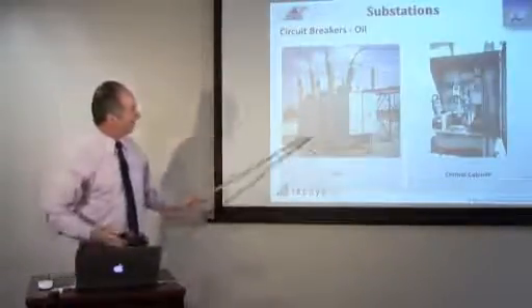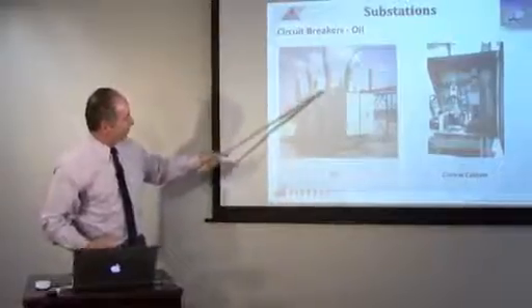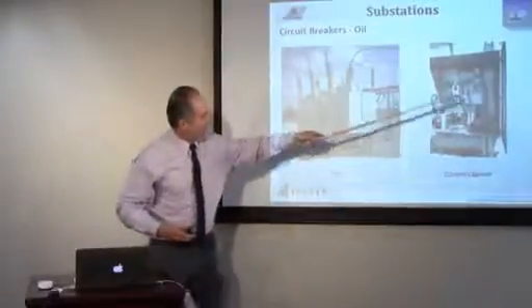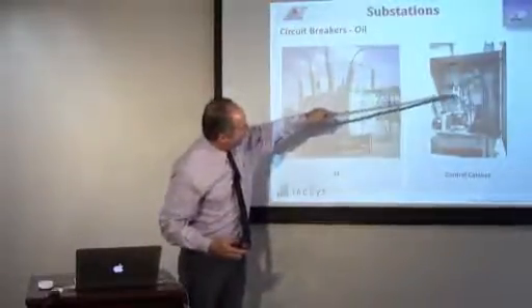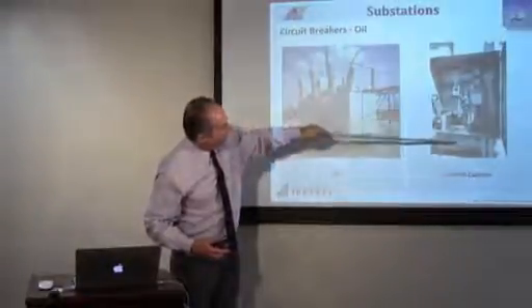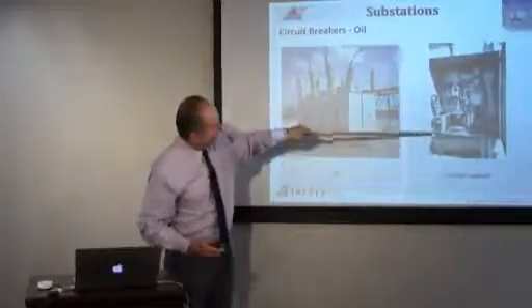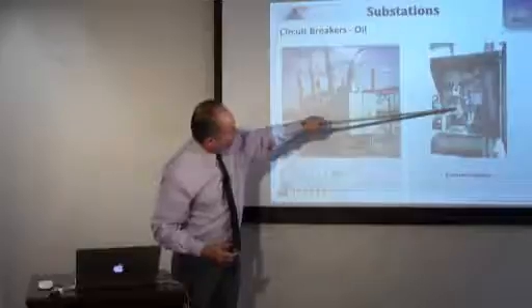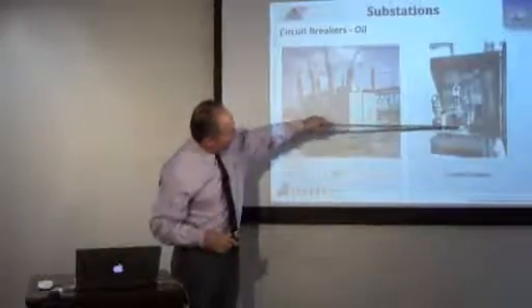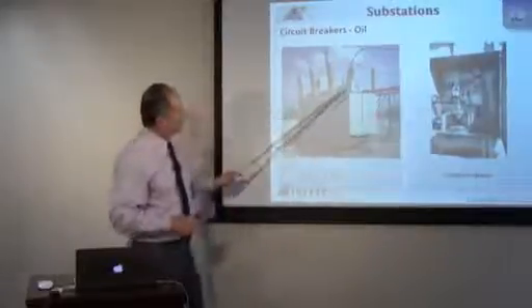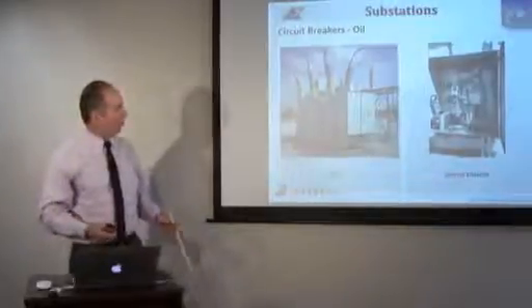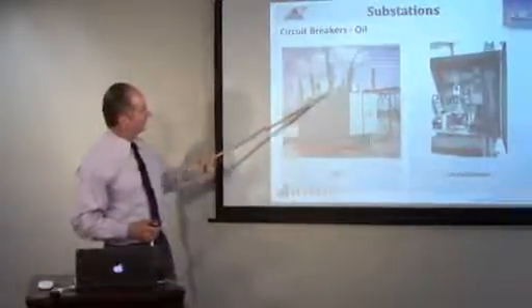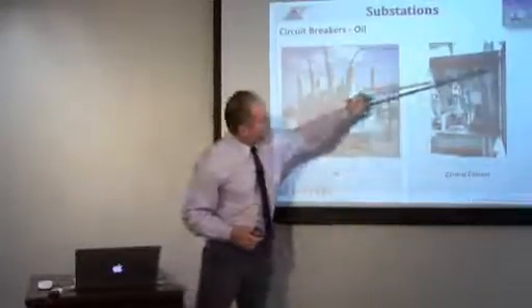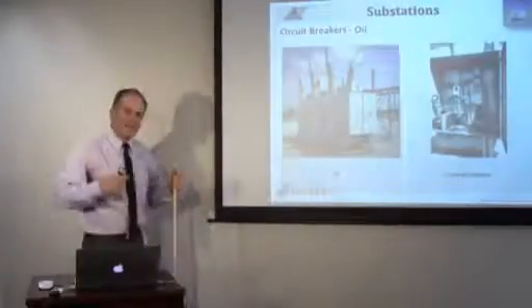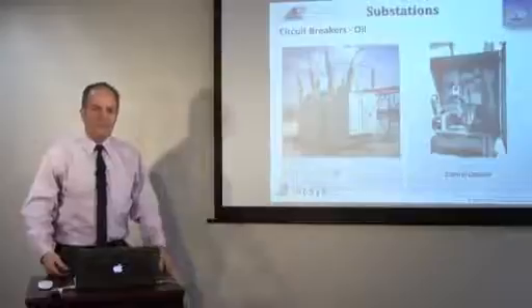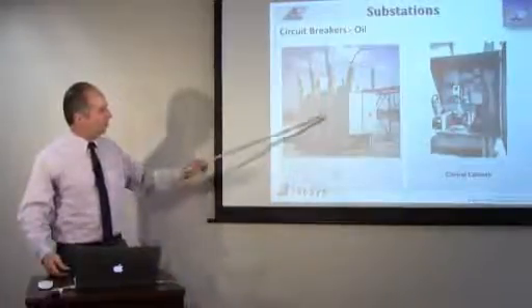Okay, and that U connector goes up through a rod, and the rod goes across the top, goes into this box, comes over here to this box, and right up in here there's a rod. You can barely see it, but there's a piston here. If you take compressed air, there's a compressor, you can put air in the bottom and it pushes the piston up, which closes the breaker, or the other way around. Or you put air in the top, it pushes that piston down. So you can make that piston go up and down, which through leverage makes the breaker open and close in oil. All the CTs are inside the unit, and all the wires are on the side here inside the cabinet for connecting the CTs to the protective relays and telecommunications and what have you. So that's an oil circuit breaker.